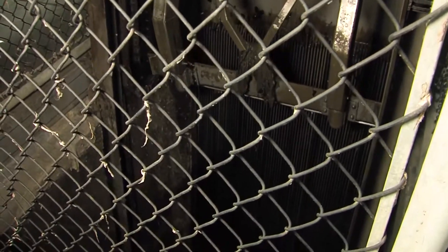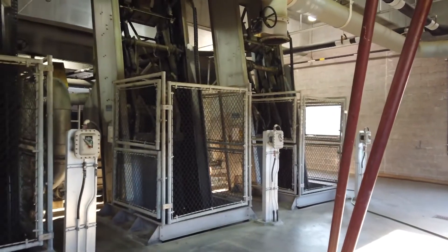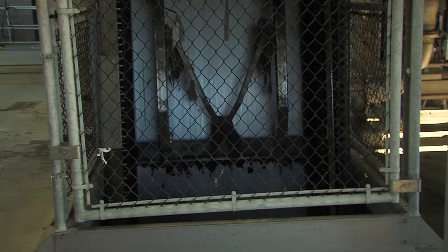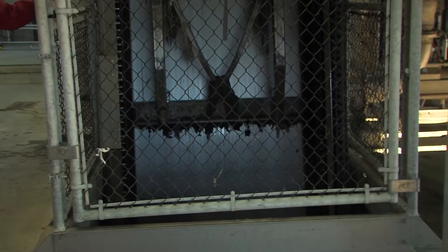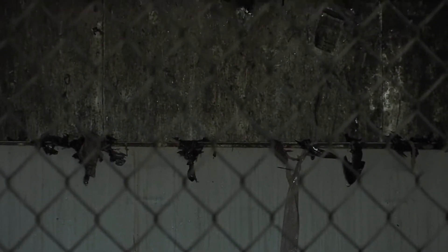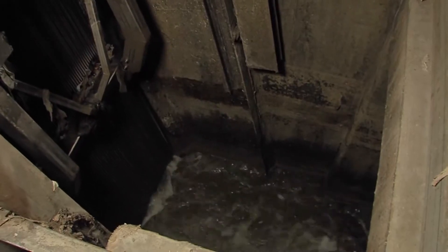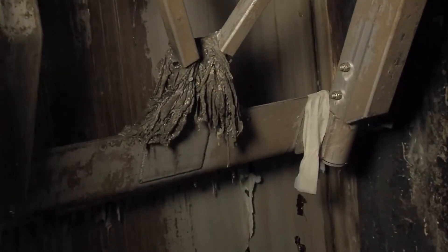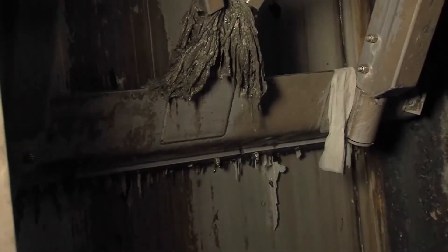The first process water goes through at the treatment plant is called a bar screen. The bar screen has a set of bars erected in the flow that trap solids — rags, sticks, stones, nuts, bolts, rocks — anything larger than a quarter inch. The bar screen rake, which you see moving, will clear the bar screen periodically to remove those solids. We see some interesting things come through: a piece of jewelry, a deceased rodent, a snake. Anything larger than a quarter inch is trapped by the bar screen.